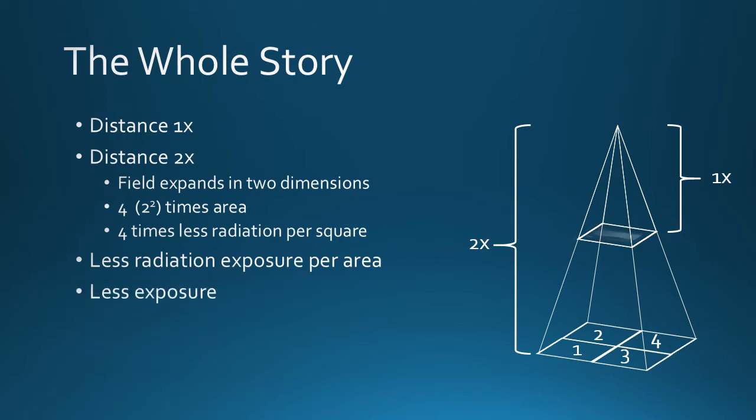Each square receives one quarter of the amount of radiation. If we were to radiograph a foot at the new distance without compensation, it would be underexposed by a factor of four times. And from the standpoint of personal dose, it would be reduced by a factor of four times.